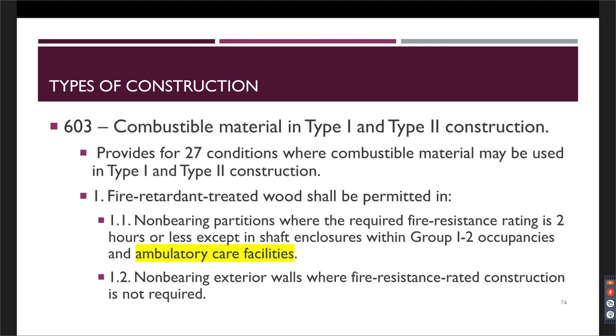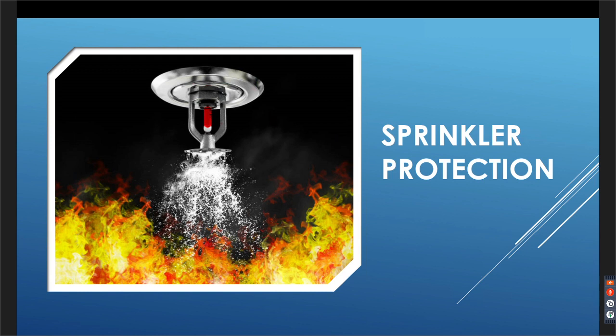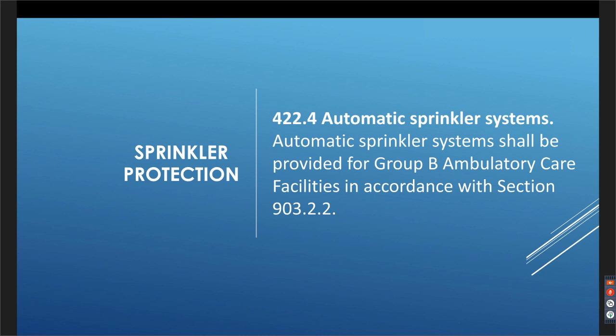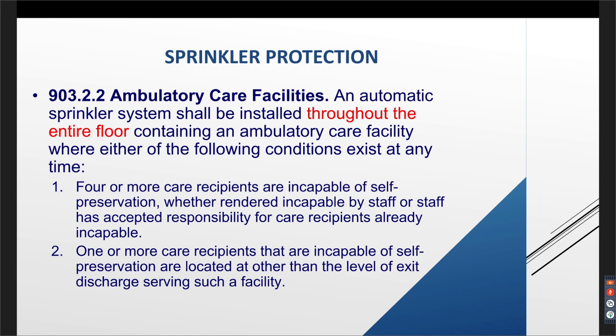us up into the next section in effective use of the code, which is determining whether a building is sprinklered or not. So we'll talk about sprinkler protection. Starting off with the B occupancy, ambulatory care facilities, section 422 has a requirement for automatic sprinklers and requires that ambulatory care facilities comply with section 903.2.2. If I jump to 903.2.2, it says an automatic sprinkler system shall be installed throughout the entire floor of a building containing an ambulatory care facility where either of the following conditions exist. So Nancy alluded earlier, if you have 4 or more care recipients, so in this case 4 or 5 incapable of unassisted self-preservation, sprinklers would be required. Or if you have 1 or more above the level of exit discharge. So this again is throughout the floor where the care recipients are located, not the entire building.